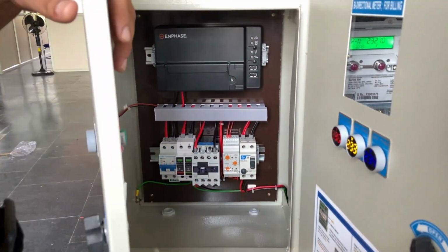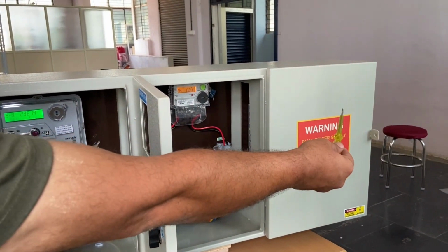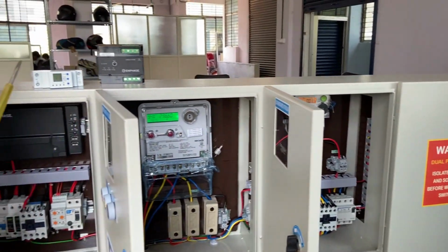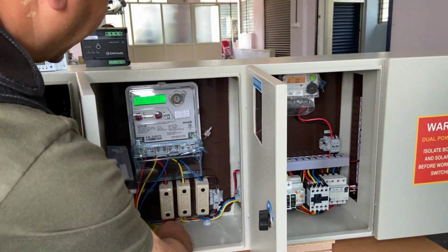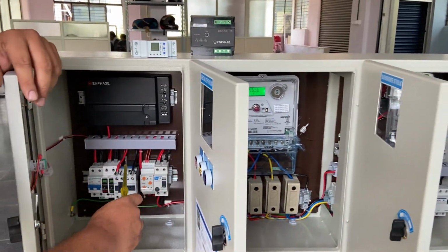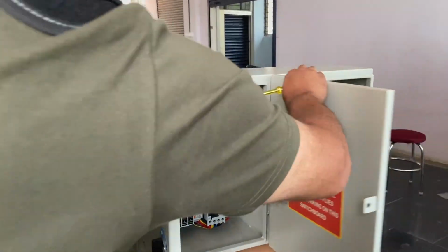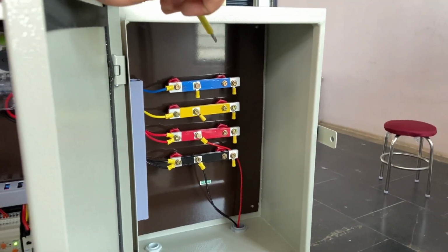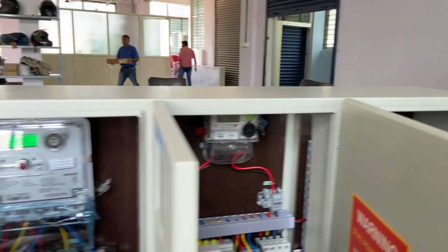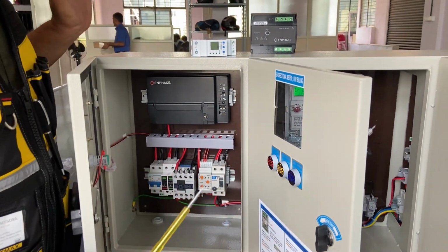This senses the bus bar voltage, again it's a grid voltage. So, there is a dual protection. This relay itself will cut off if the voltage on the incoming side is higher. There is an additional relay which is now sensing the bus bar voltage, that is this voltage here. So, if this voltage goes more than a certain value, this relay is going to actuate this contactor and open up the circuit.